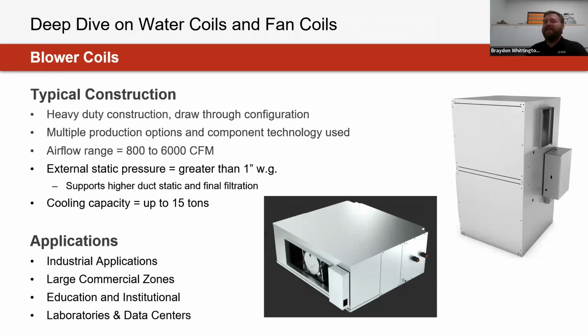Yeah. And shifting into the last components of what we'd see here, with just blower coil units. So these ones also have versions of horizontal as well as vertical configurations. With these ones though, now we're getting up to 15 tons, let's say, of cooling, or 6,000 CFM, and a much greater amount of static that we're able to handle within these systems. Commonly, let's say, installed in a maintenance closet or a bit further from the space, just for some of those considerations of noise for that product, because it's almost acting like a mini air handler for this system.